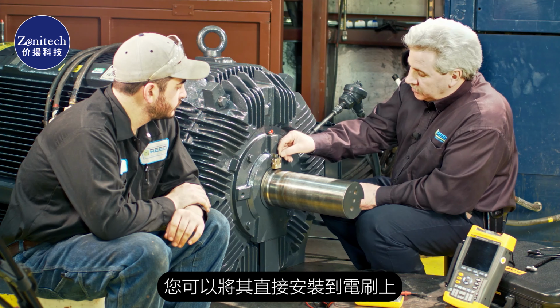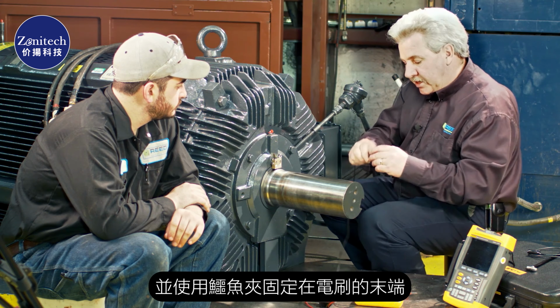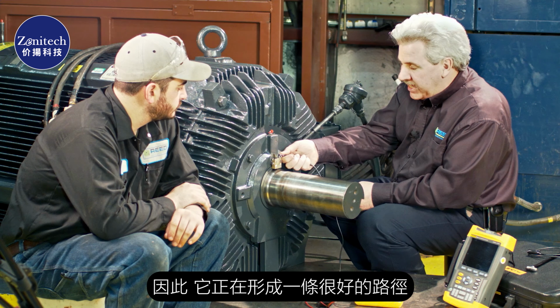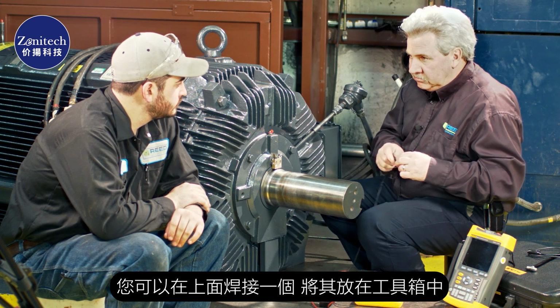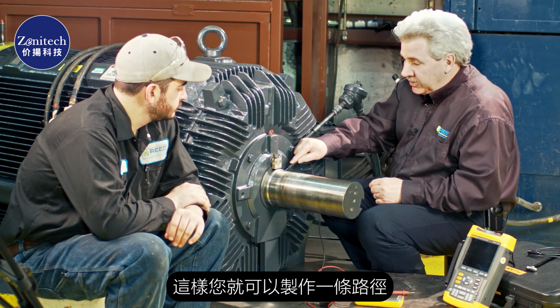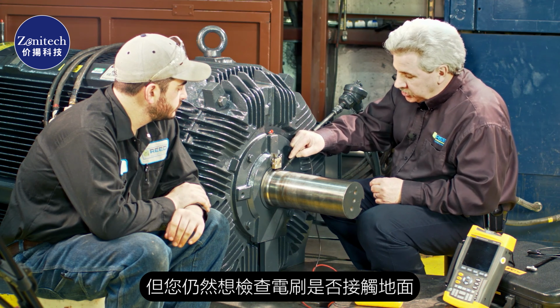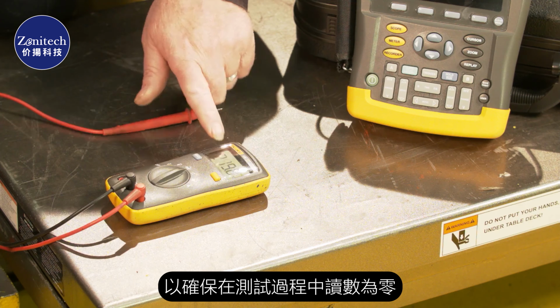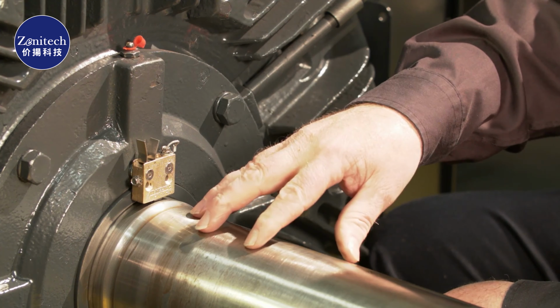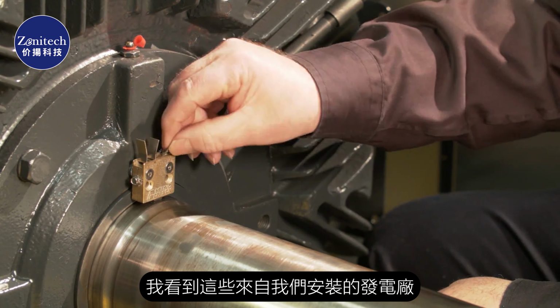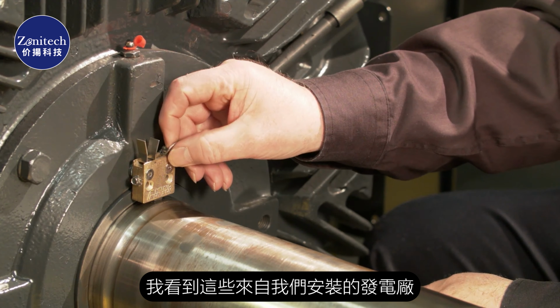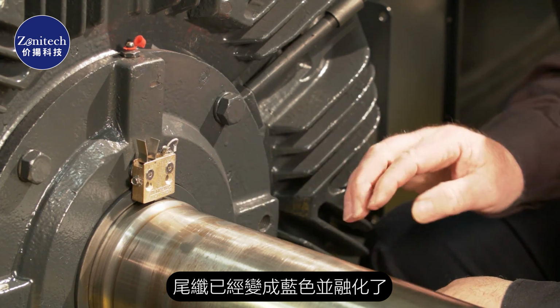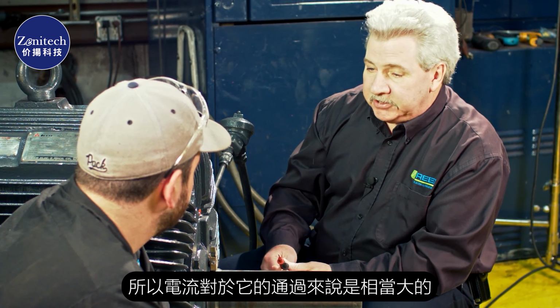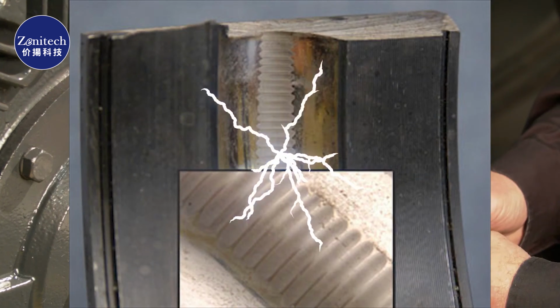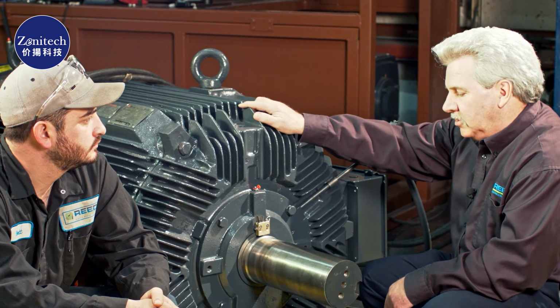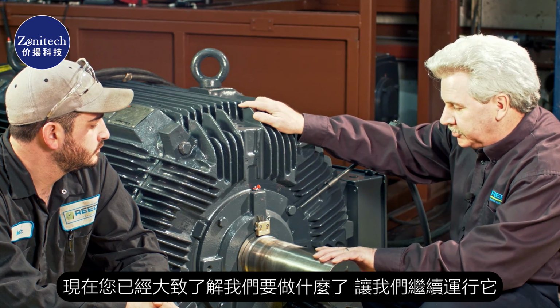You can mount it directly to a brush and use an alligator clamp onto the end of this, so it's making a nice path. You could solder one on it, keep it in a toolbox and have it so that you're making a path, but you still want to check with that brush touching to ground to make sure that you have a zero reading during the test. I have seen these come in from a power plant that were mounted on by us, and that pigtail had turned blue and melted off. So the current was pretty substantial for that to pass through. Okay, Brett, now you understand pretty much what we're going to do. Let's go ahead and run it.